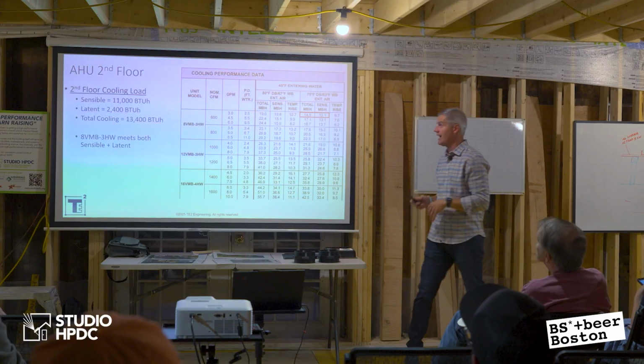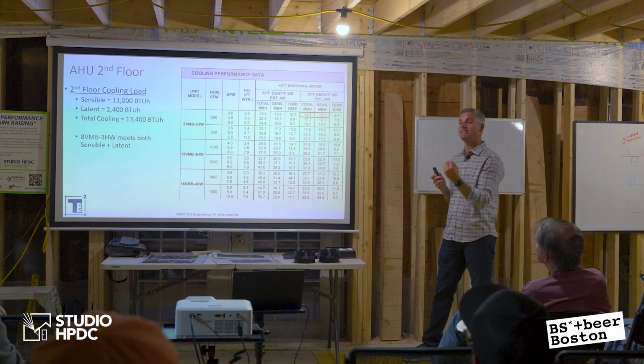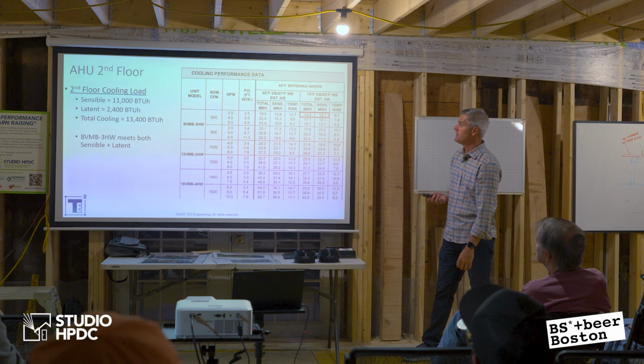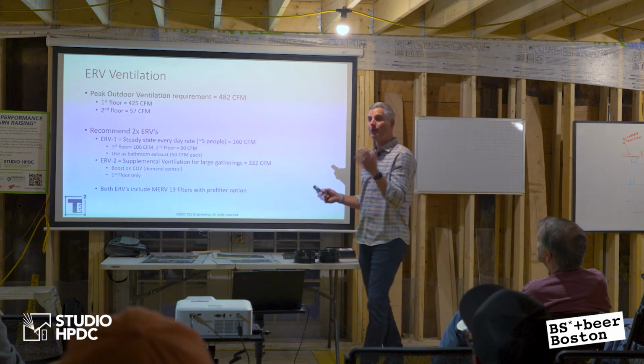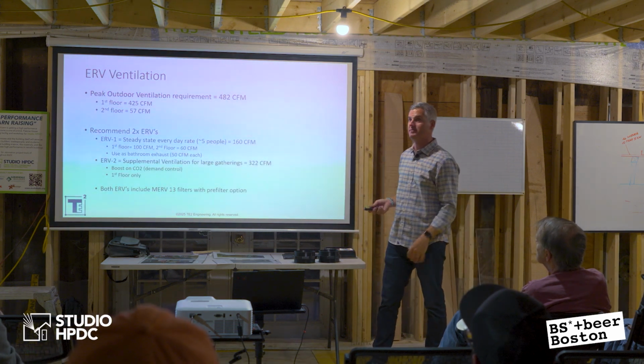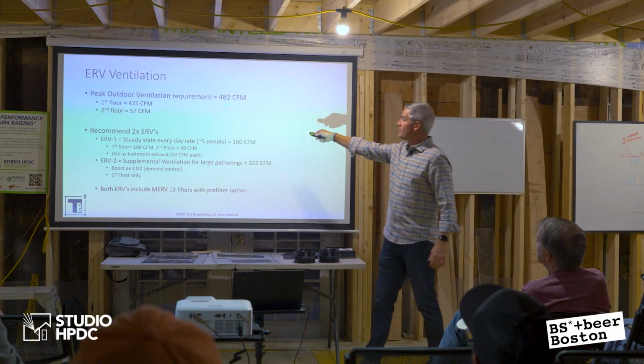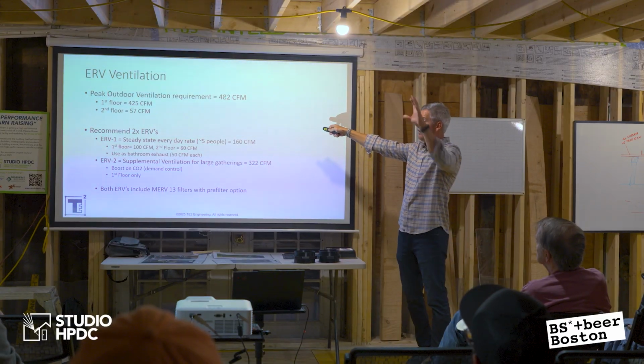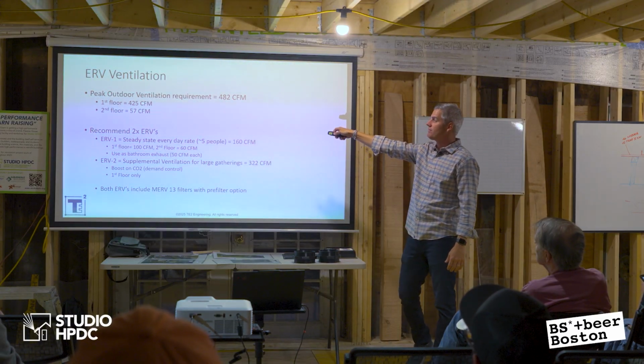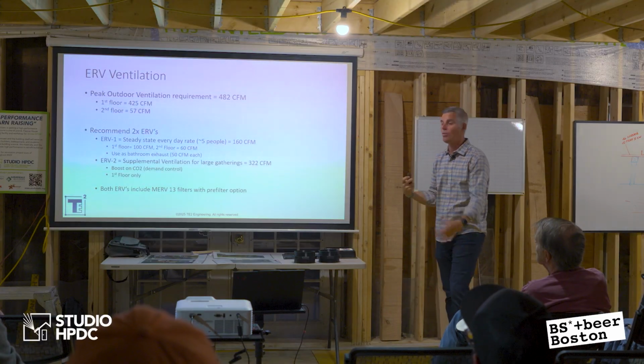Yep. Yeah, it needs to have control and sensing of the humidity in this space. Okay, so how would I handle the ERV in this space, or the ventilation in this space? The peak outdoor ventilation rate is 482 based on all that people, right? 425 for the first floor, 57 for the second floor. So what would I do, right?